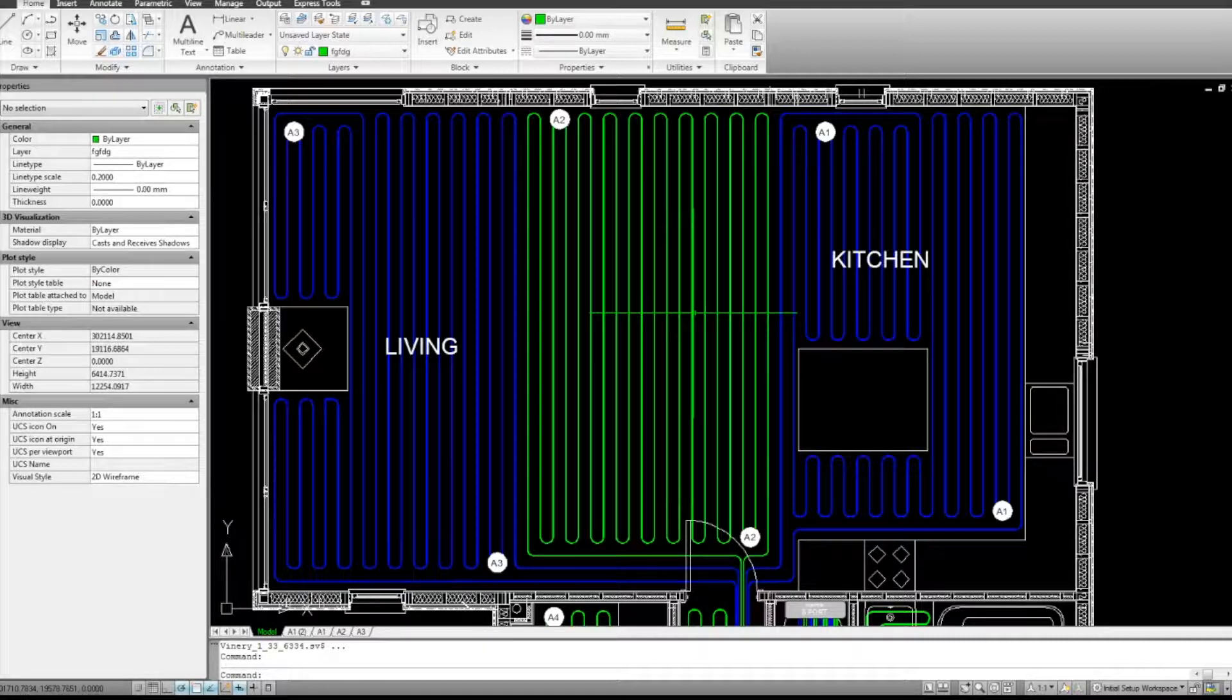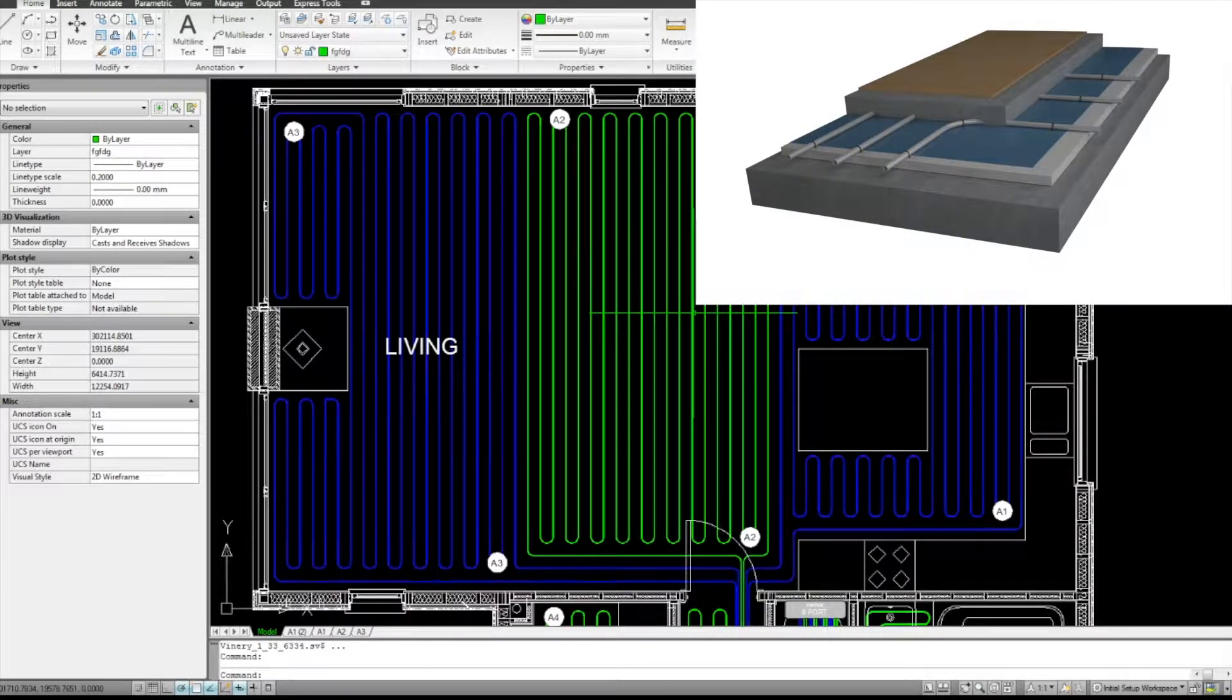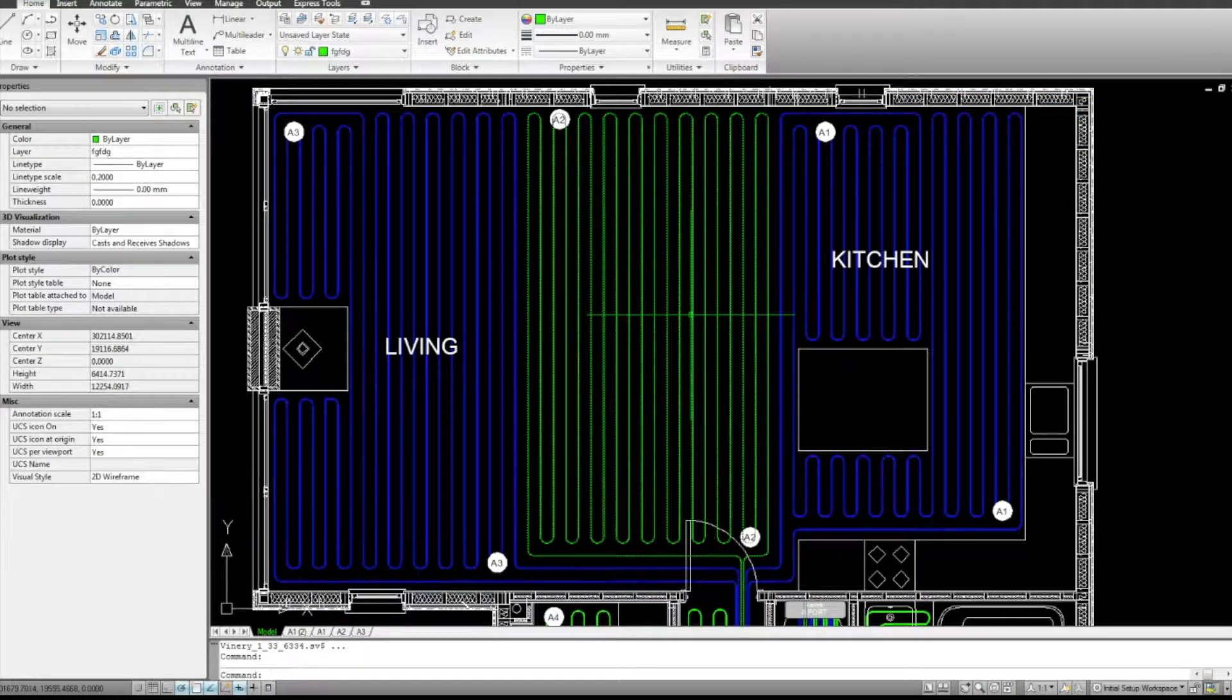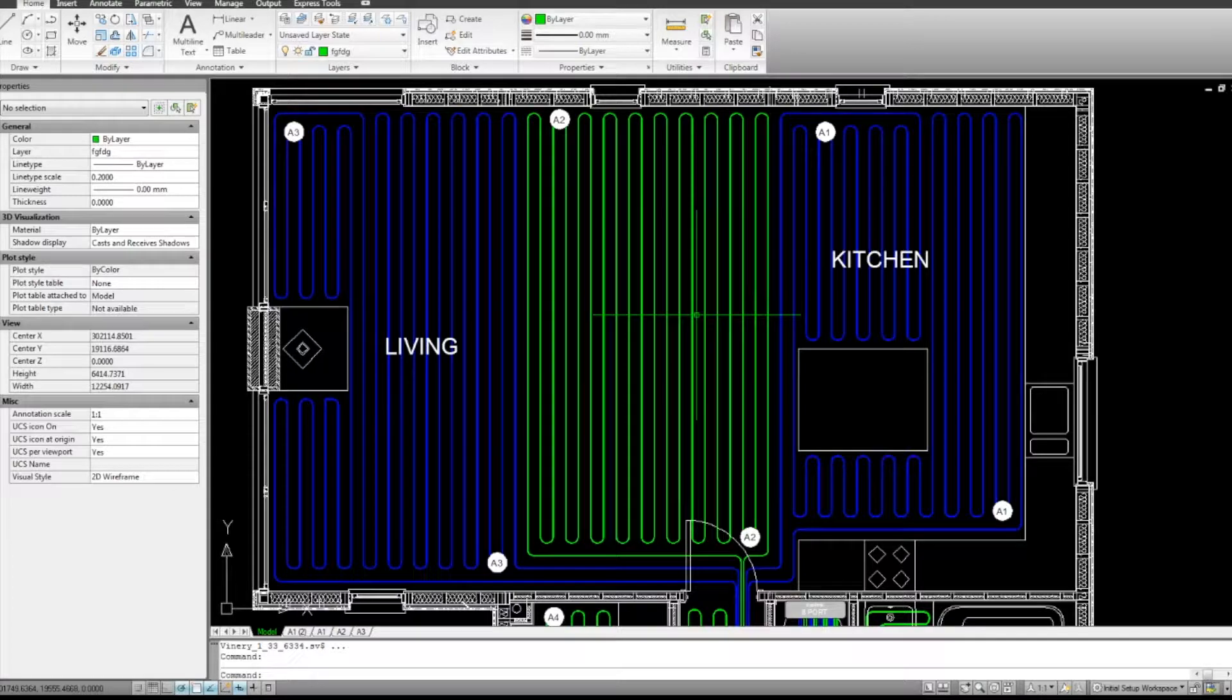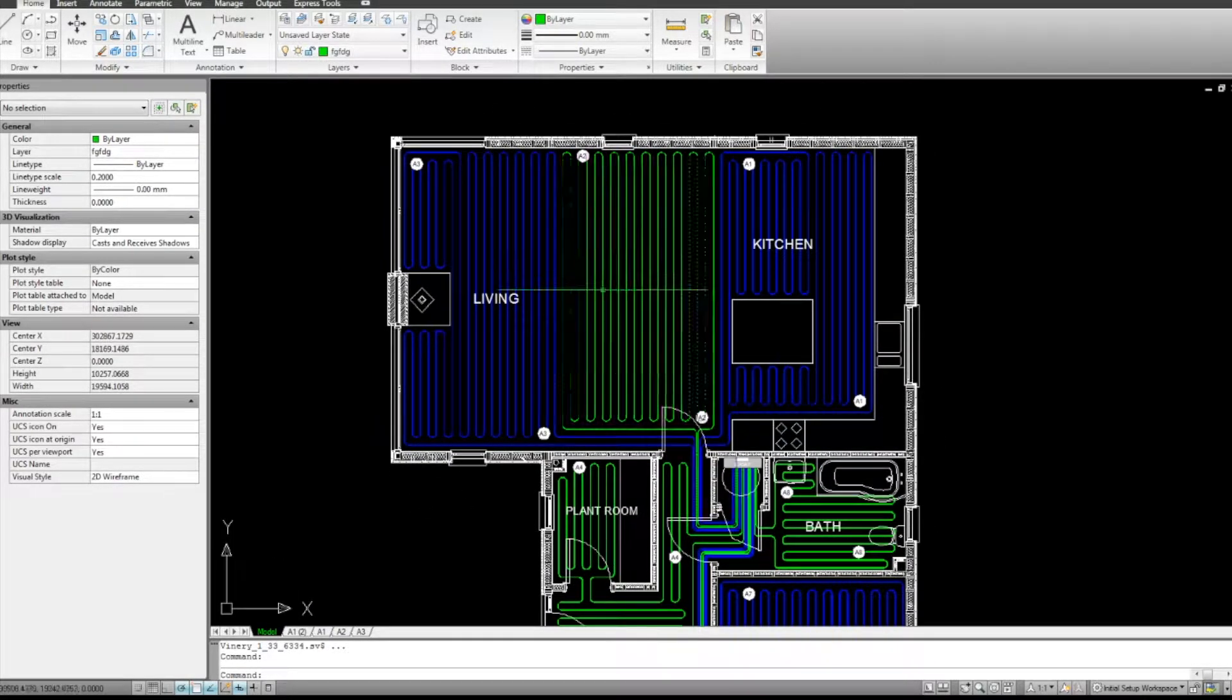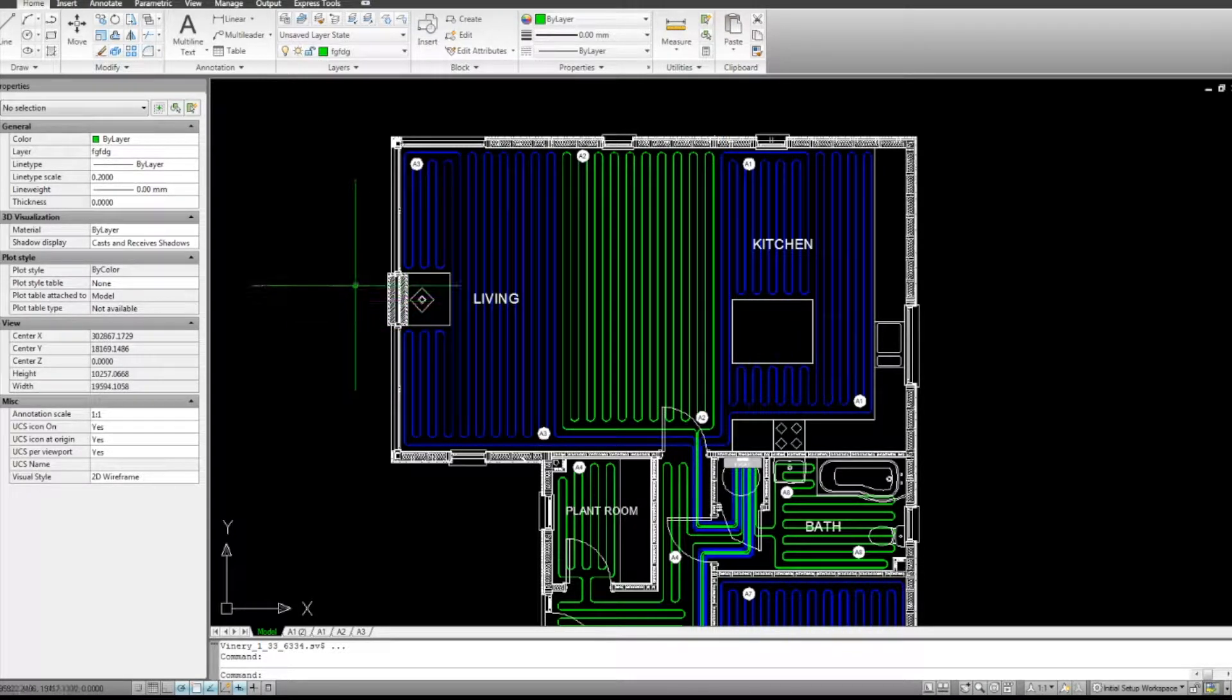For example, this system is within a screed. I'll put a picture on the screen so you can see what I mean. And you're limited generally between 100 and 140 metres is an absolute maximum. Generally 100 metres is the maximum length. So that's why we've got three circuits in this particular room.